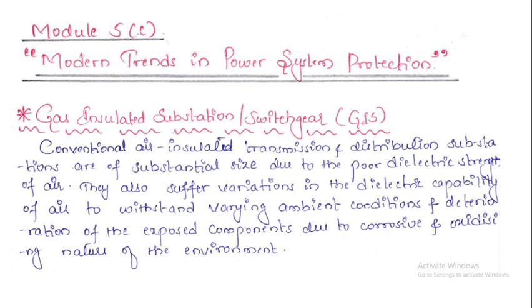So we'll begin with the C section of the fifth module, modern trends in power system protection. We have the conventional substation where air is acting as an insulation medium, the air cooled substation. All of them are called air insulated substations, where air will be acting as an insulating medium between the equipments. Now compared to that, what is the necessity of using this gas insulated substation? That we need to understand. This is a gas insulated substation, or simply called a switchgear. In short, it is called a GIS.